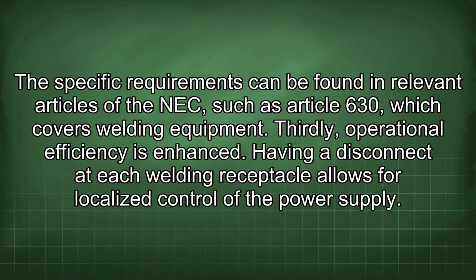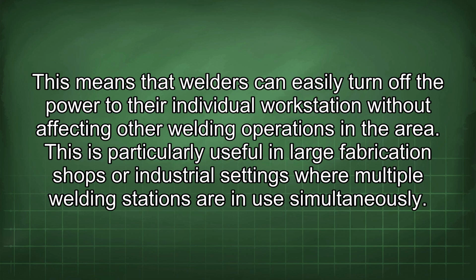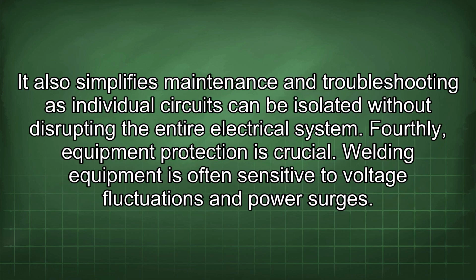Thirdly, operational efficiency is enhanced. Having a disconnect at each welding receptacle allows for localized control of the power supply. This means that welders can easily turn off the power to their individual workstation without affecting other welding operations in the area. This is particularly useful in large fabrication shops or industrial settings where multiple welding stations are in use simultaneously. It also simplifies maintenance and troubleshooting as individual circuits can be isolated without disrupting the entire electrical system.